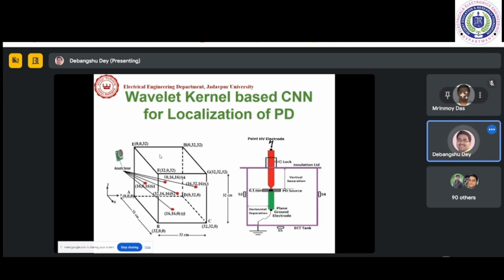So here I'm showing one problem. This is a box, and this box is a transformer - an electrical transformer, a model transformer. Within the box, anywhere there can be a partial discharge, so the locations are much more complex. Within this box, anywhere the partial discharge may occur, and partial discharge will throw you some signal - it can be electromagnetic, acoustic, or ultrasound.